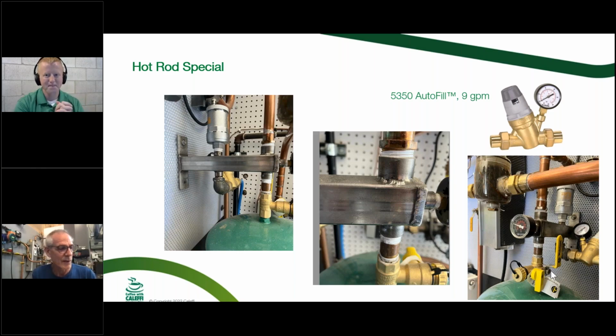But I would say the pinholes are probably the most common if you've got non-barrier tubing in the system. I've seen tanks within a year start to get little blisters on the paint and a pinhole because they're getting all the oxygen in there. Undersizing your tank, where the diaphragm is shoved way up beyond its comfort range, will shorten the life. And like Cody said, dirt laying on the diaphragm, so as it moves up and down, the dirt's kind of eroding through it. Those are all things that can shorten the life of it. It's a thin steel tank. It's not going to be a 100-year product. I mean, let's be realistic on what this tank really is made out of and what it's intended to do.